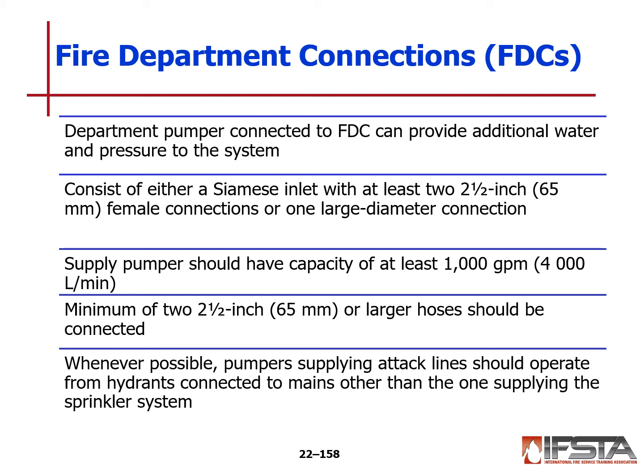Fire department connections, the department pumper connection, or the FDC, can provide additional water and pressure to the system. This is what we connect to. Usually it's a Siamese inlet with at least 2.5 inch female connections, or it could be one large diameter connection such as 5 or 6 inch hose. And we use this to supplement the pressure. We'll hook into it with the pumper. We can then boost the system to help maintain that proper PSI. A minimum of 2.5 inch or larger hoses should be connected. Whenever possible, pumpers supplying attack lines should operate from hydrants connected to mains other than the one that is supplying the sprinkler system, if at all possible.